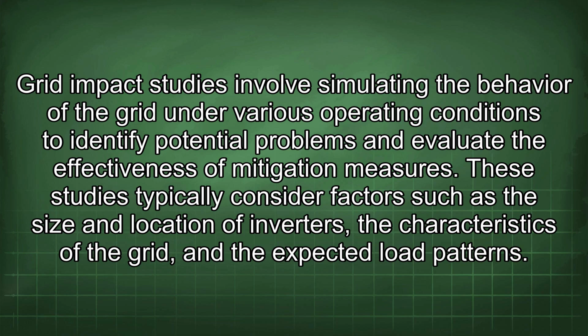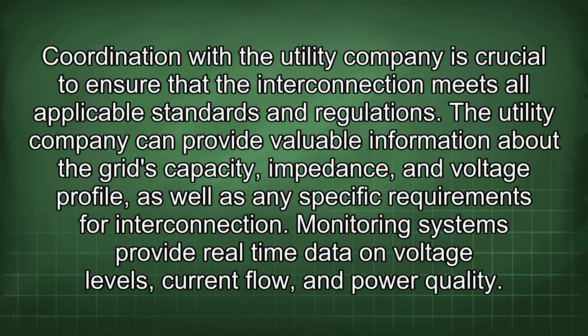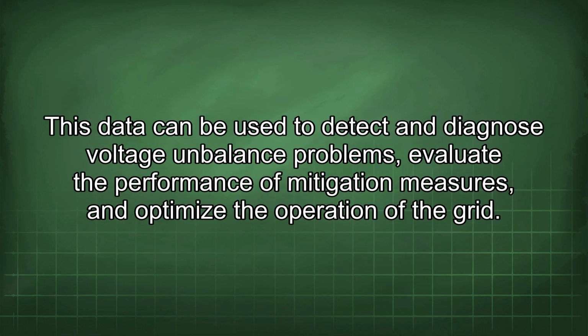These studies typically consider factors such as the size and location of inverters, the characteristics of the grid, and the expected load patterns. Coordination with the utility company is crucial to ensure that the interconnection meets all applicable standards and regulations. The utility company can provide valuable information about the grid's capacity, impedance, and voltage profile, as well as any specific requirements for interconnection. Monitoring systems provide real-time data on voltage levels, current flow, and power quality. This data can be used to detect and diagnose voltage imbalance problems, evaluate the performance of mitigation measures, and optimize the operation of the grid.